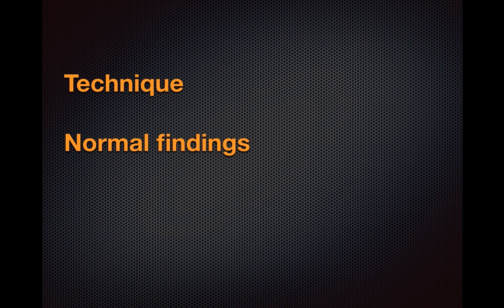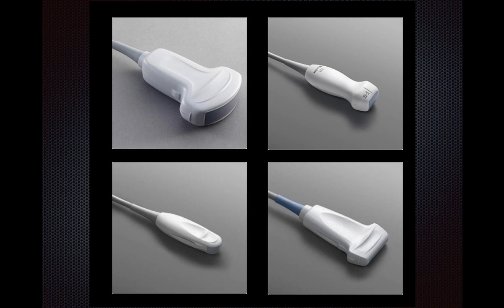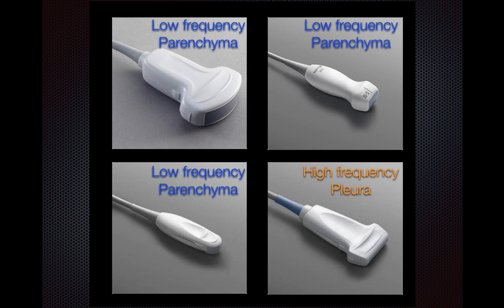In terms of transducer selection, there are a number of transducers to consider. The top left is the curvilinear transducer, often called the abdominal probe. The top right is the phased array, or cardiac transducer. There is also a micro-convex transducer and a linear transducer. The main consideration in deciding which to use is frequency. The curvilinear, phased array, and micro-convex are all low-frequency transducers, while the linear transducer is high-frequency.